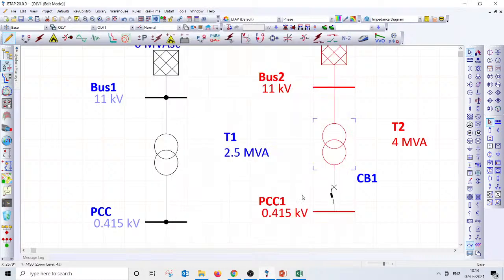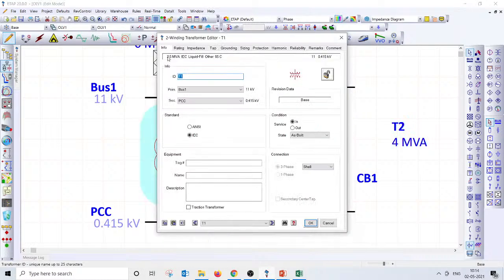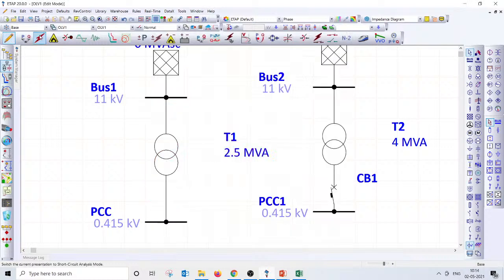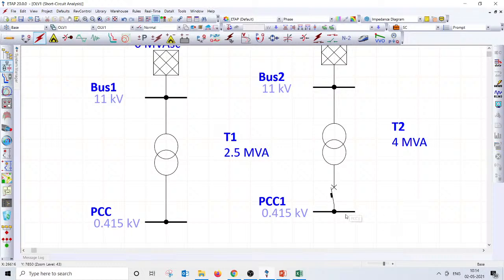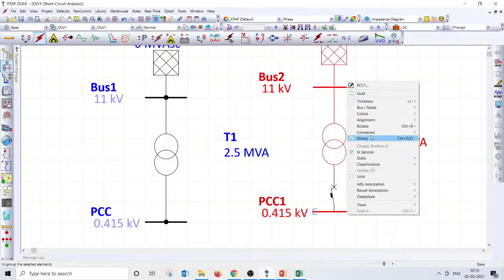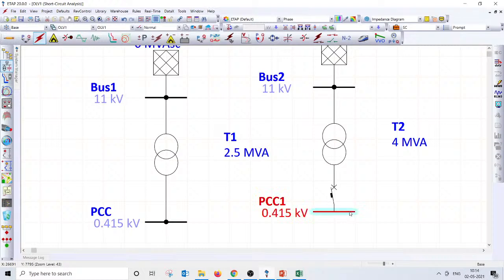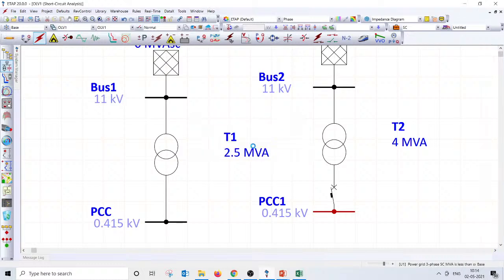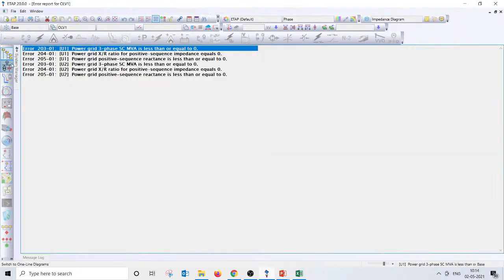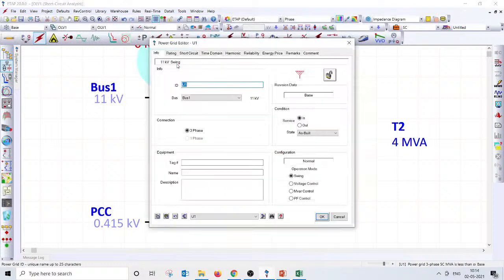Having said that, let's look into the short circuit study and find out what the fault current may be if we have a 4 MVA transformer. What's the mistake which I have made? I have not given the grid short circuit current.